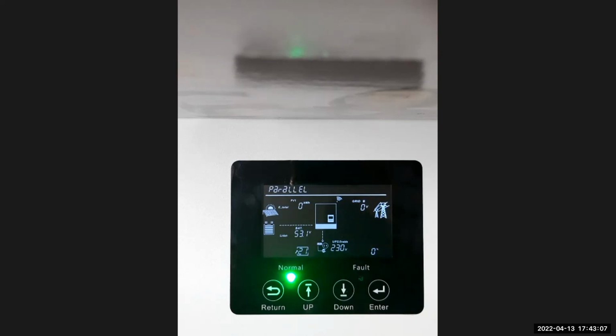Now, setting number 21 is parallel settings. Parallel settings on these inverters is quite easy on the screen. You don't have to do it on the computer. This inverter is set to no parallel. There's 1 pH, which means single phase parallel, 3 pH, which means 3 phase parallel, and no parallel. If I go to a 3 phase parallel system, you set your phases here, 1, 2, and 3. That's S, T and R on the phases, but you can do it on the screen. I'm just going to put it onto no parallel system.